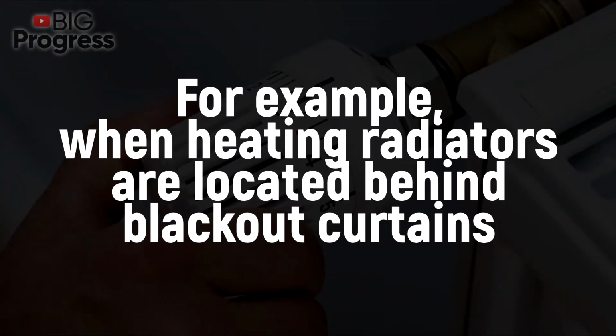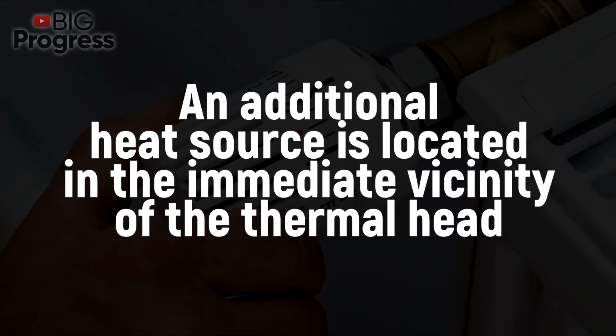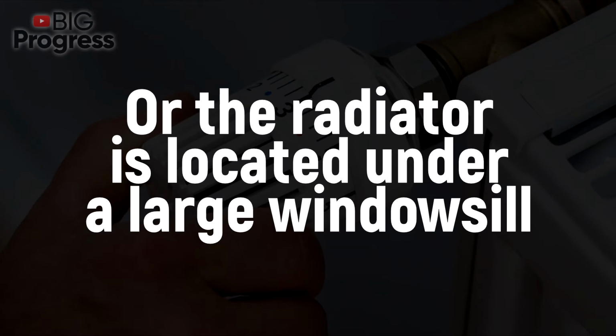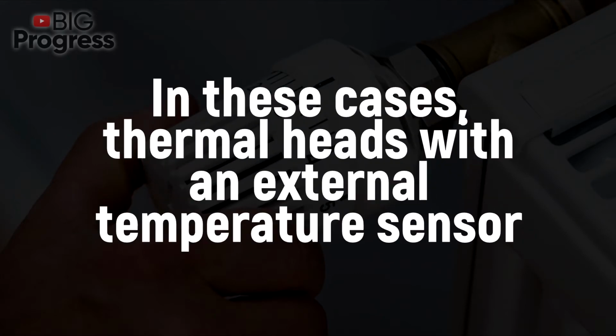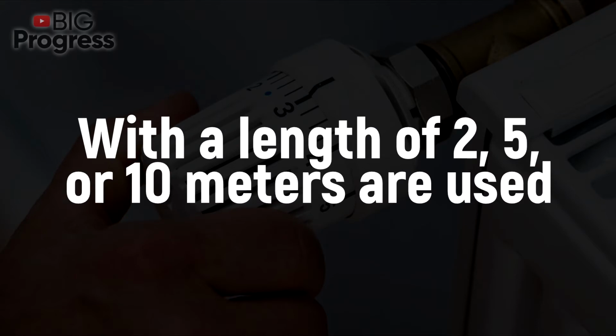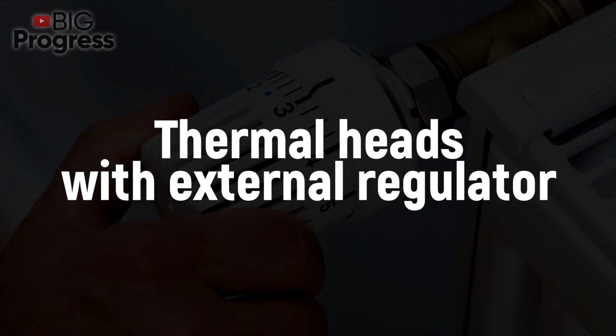For example, when heating radiators are located behind blackout curtains, an additional heat source is located in the immediate vicinity of the thermal head, or the radiator is located under a large windowsill. In these cases, thermal heads with an external temperature sensor with a length of 2, 5, or 10 meters are used.